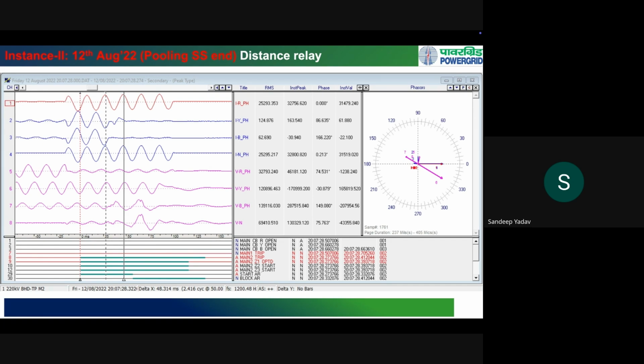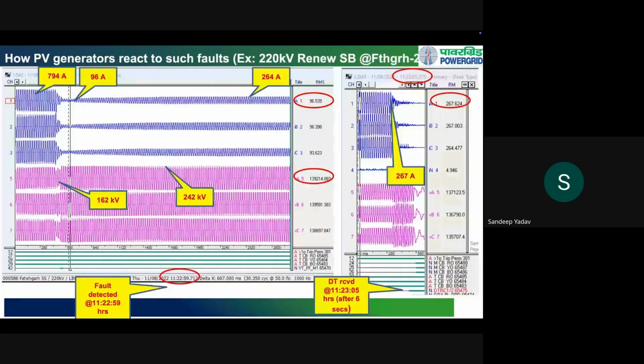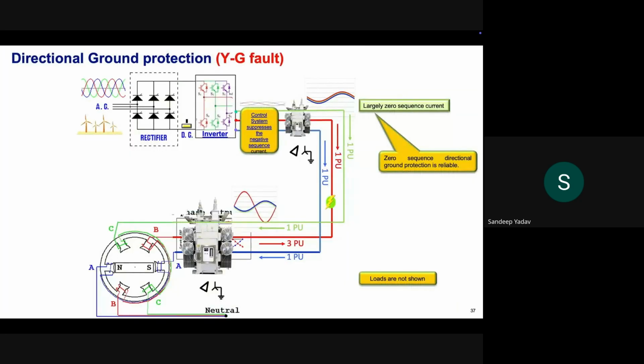Yes, this is another example of a phase to ground fault. So let's go back to the slide for phase to ground fault. Yeah, this is a phase to ground fault. So in a phase to ground fault, what will happen? In the faulty phase, the current will be very high. If we look at the grid side, the faulty phase current will be higher. However, from the solar plant or the IBR side, all we would expect is zero sequence current. So all the three phases R, Y, and B will have almost the same magnitude, and they will be in phase. Let's see.